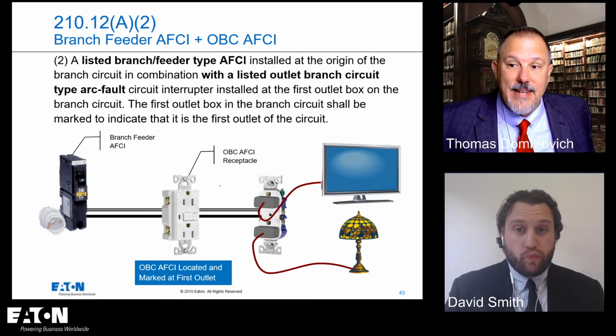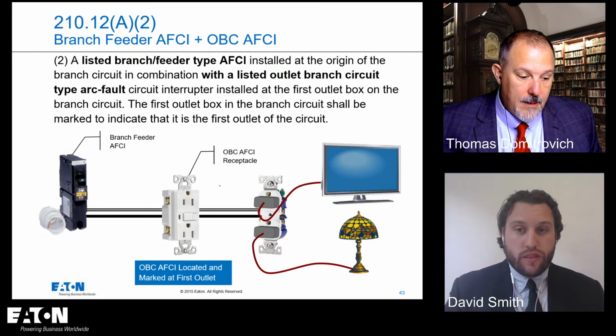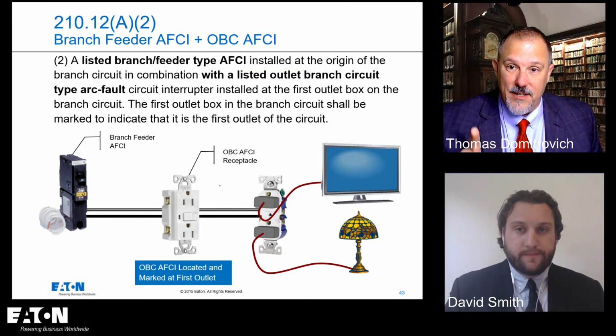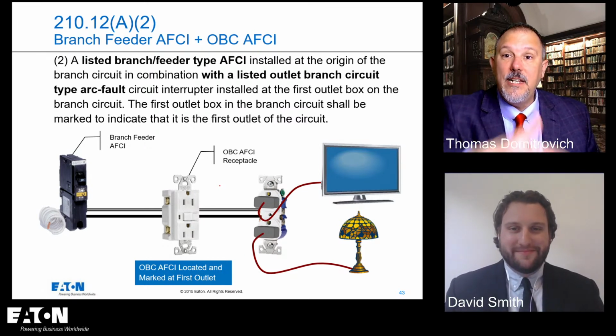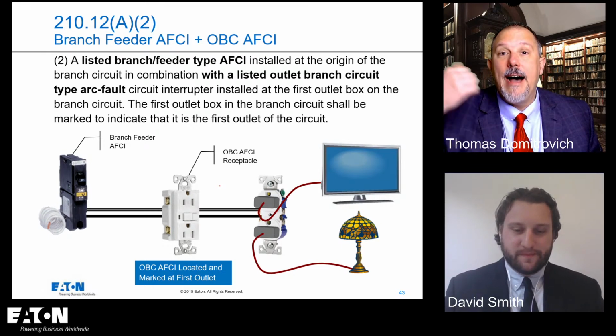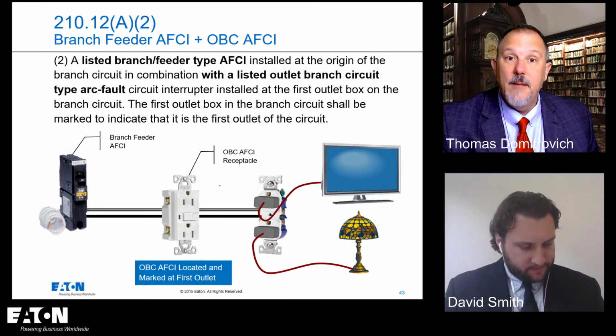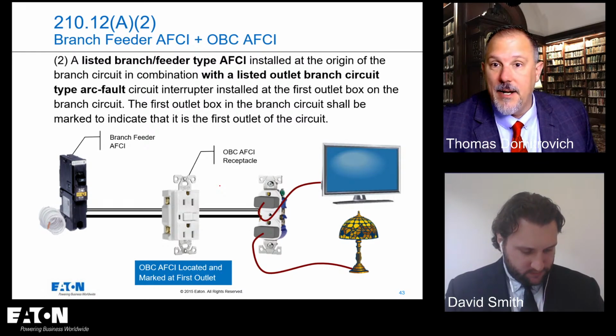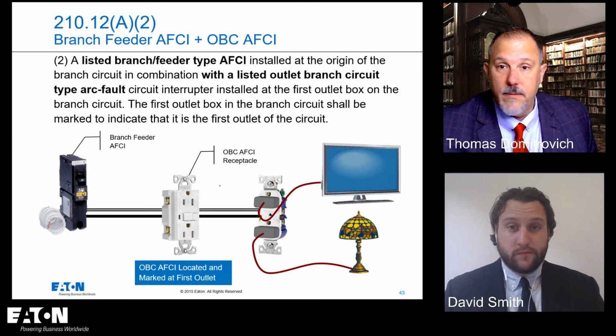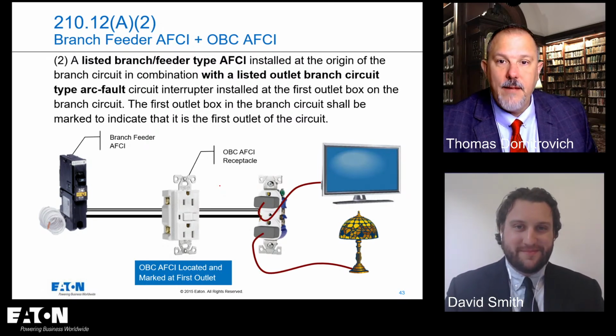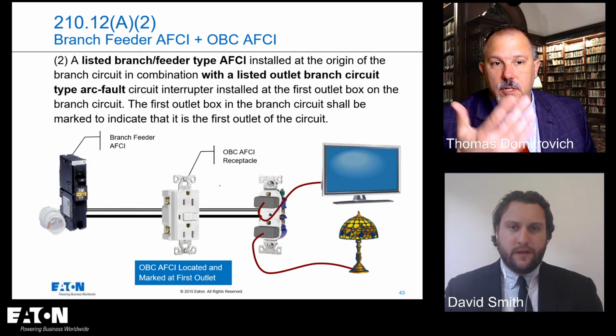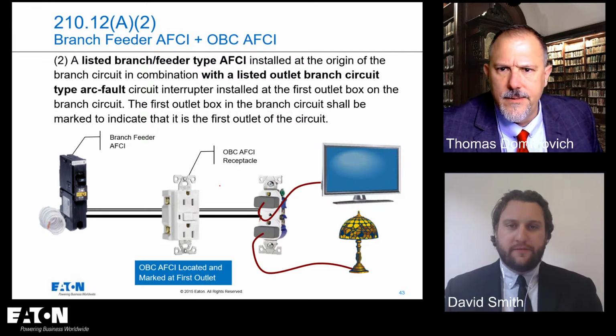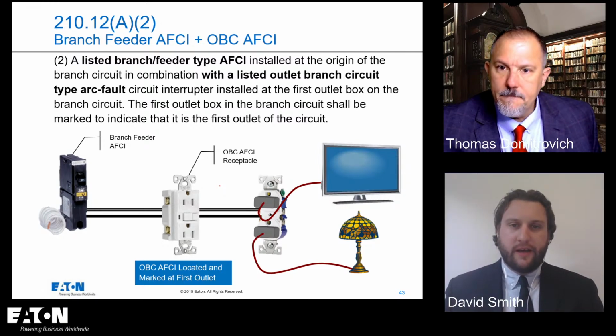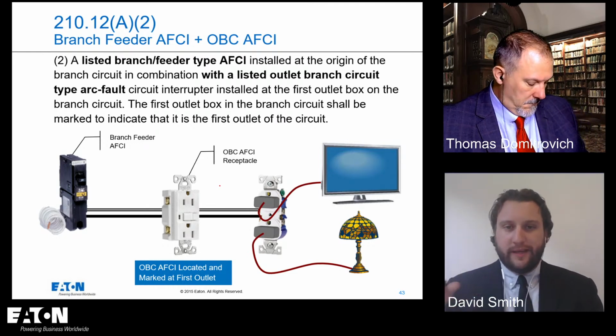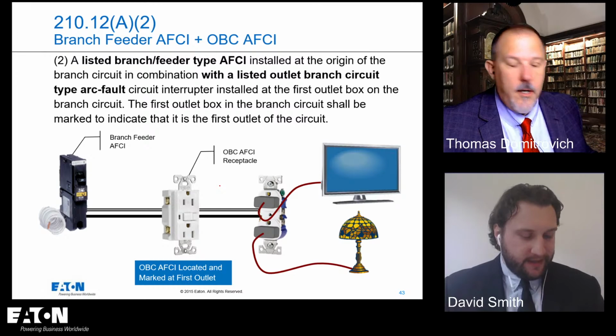No, Ryan Jackson, standards are not viewable for free. But you know what UL does, they publish, it used to be the white book, and it's now product spec. So what they do is they give you the information you need out of the standard to properly apply the product. Because if you viewed the UL standard, I've looked at UL standards and I can't figure them out. So they repurpose that and try to give you what you need in the white book, which is now UL product spec or whatever they call it. Yeah, I think you can look that stuff up through the product type, right? Like I think I've done that a good bit. I can't remember, but it's normally 4 digits of fun.